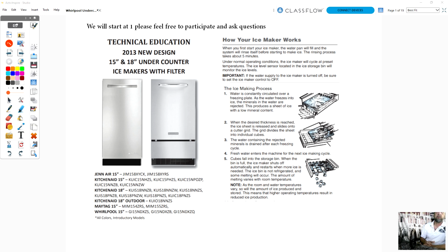How your ice maker works, basically, if we look at this image right here: this is what we call the evaporator, and it runs at about the same temperature and pressure a regular refrigerator would run. If you're using R134A, you're probably going to have a 0 psi evaporator running about 15 degrees below zero. I'll go into a little more detail, but water circulates over this evaporator, and the excess runs off into a trough that returns.